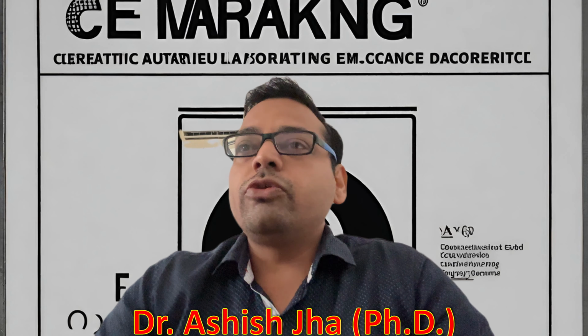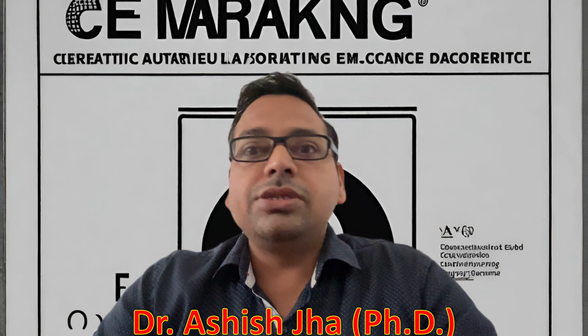First, let's understand one thing, and then we will talk about a few other things. If your medical device has the CE mark, it does not mean that the device is safe and sound. No. Any clinicians, users, or physicians deciding whether to use a medical device should not consider only the CE marking.